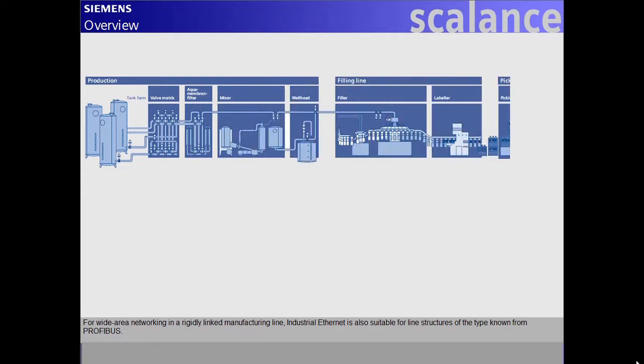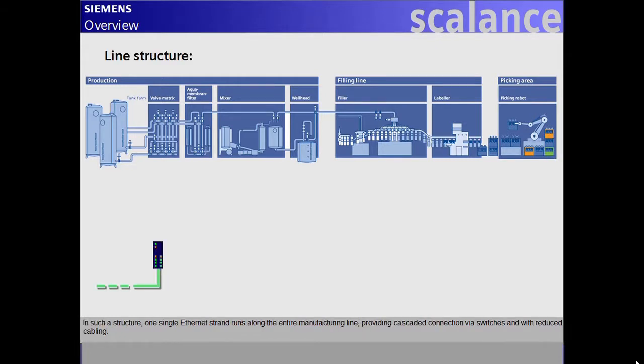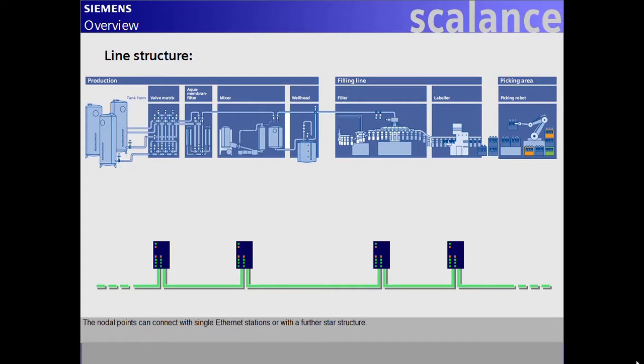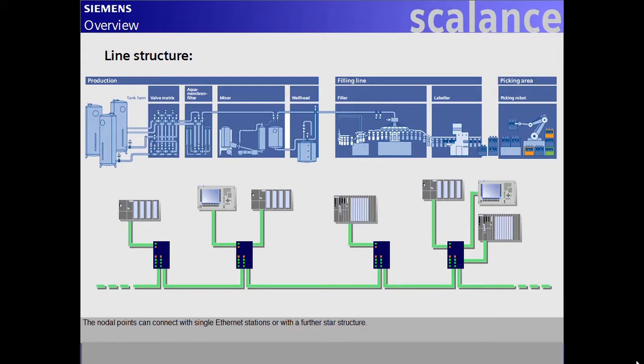industrial Ethernet is also suitable for line structures of the type known from PROFIBUS. In such a structure, one single Ethernet strand runs along the entire manufacturing line, providing cascaded connection via switches and with reduced cabling. The nodal points can connect with single Ethernet stations or with a further star structure.